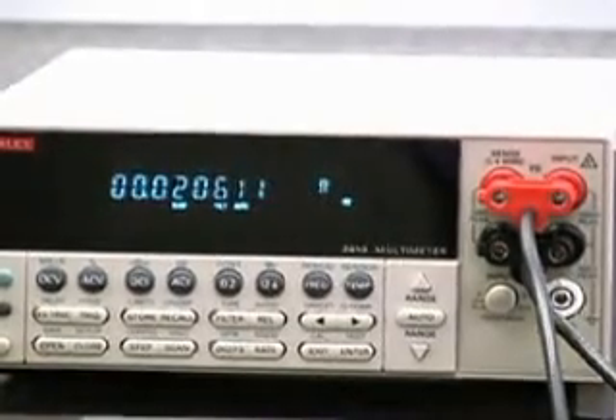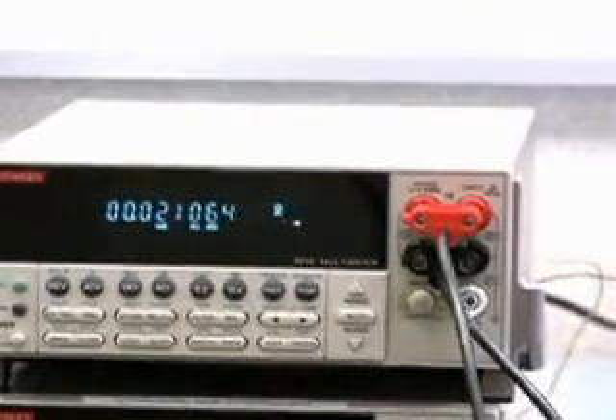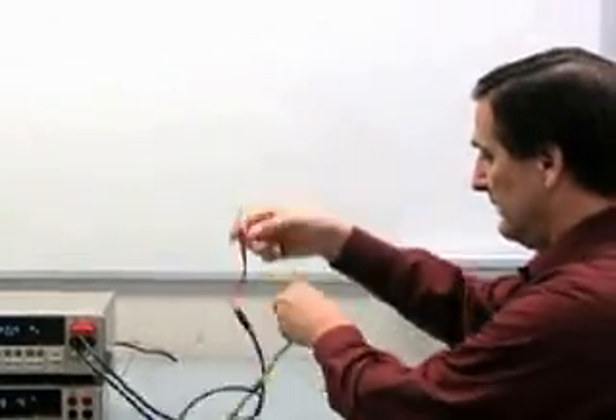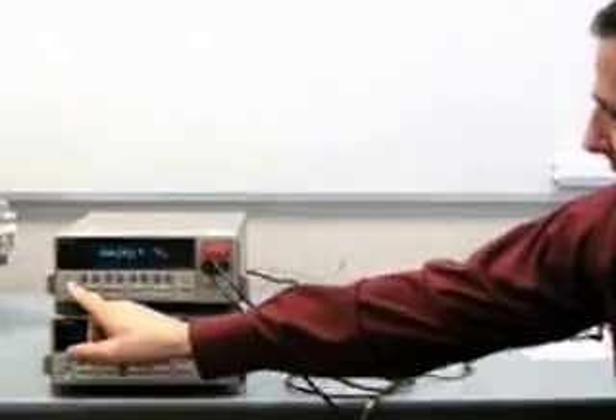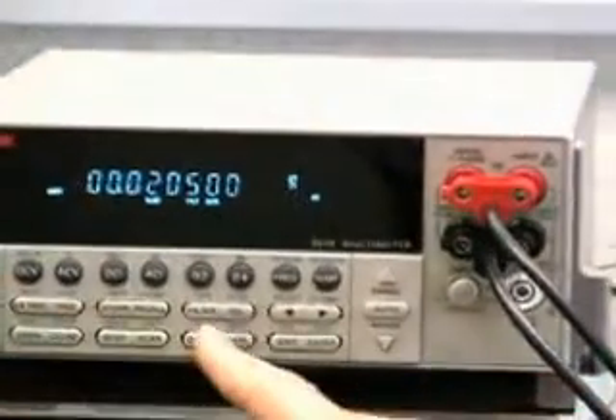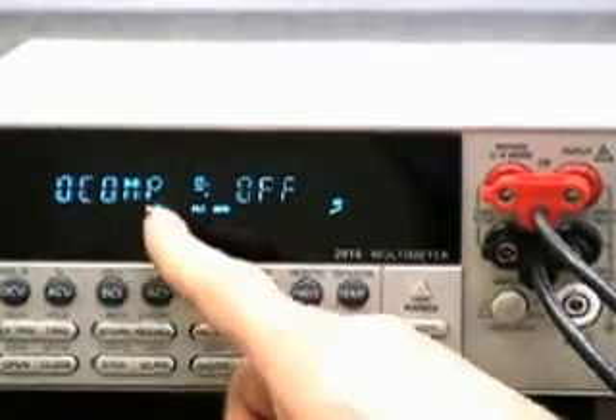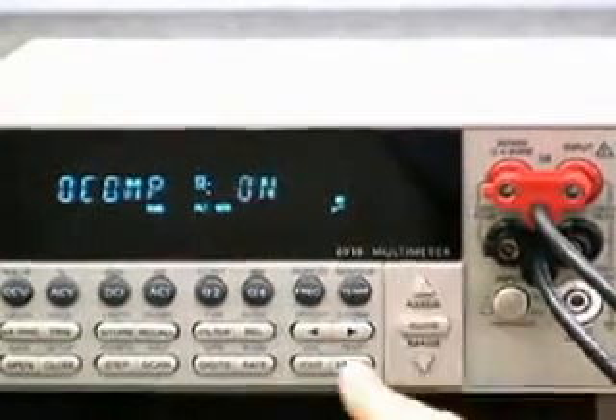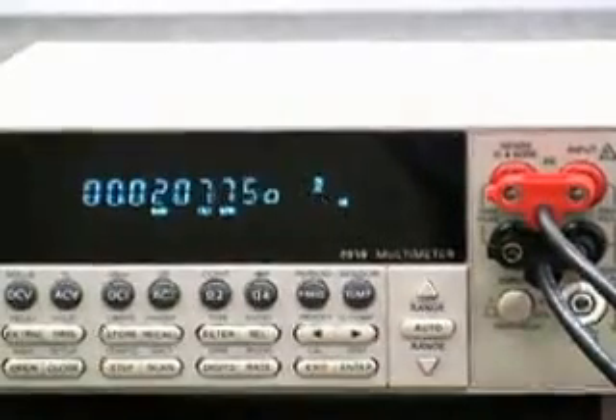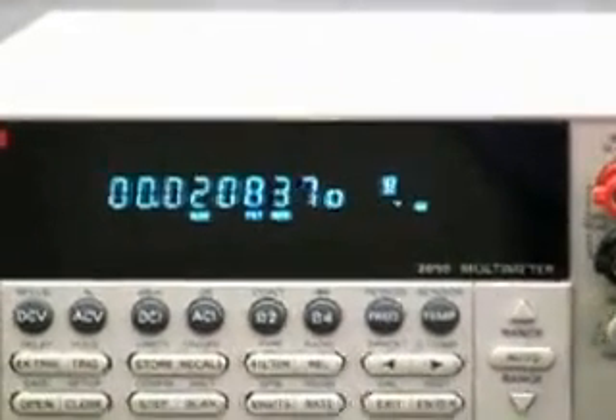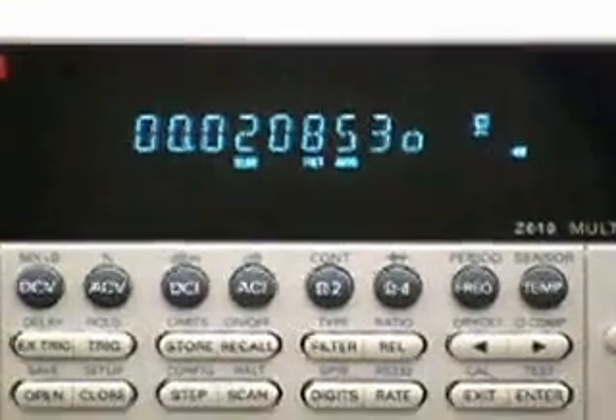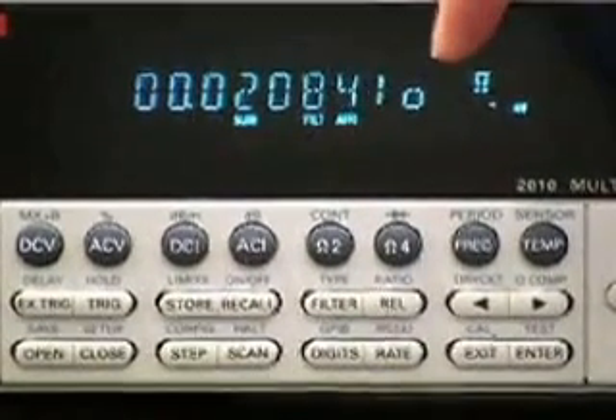One other feature that it has for measuring low resistance is offset compensation. Offset compensation means we are going to take two measurements, one with the current on and one with the current off. I'm going to put that down for a second so I can work this. And what it does here, I'll press shift, offset comp, O comp, off, on, enter. Okay, now you're seeing the 20 milliohms with the little O on the front panel saying it's an offset compensation.